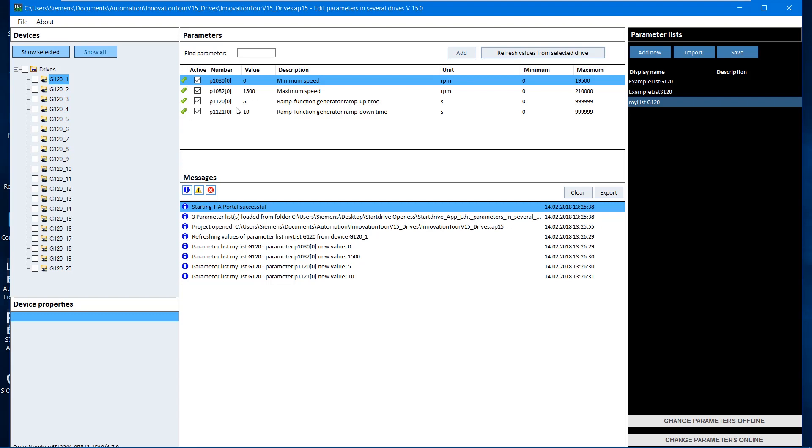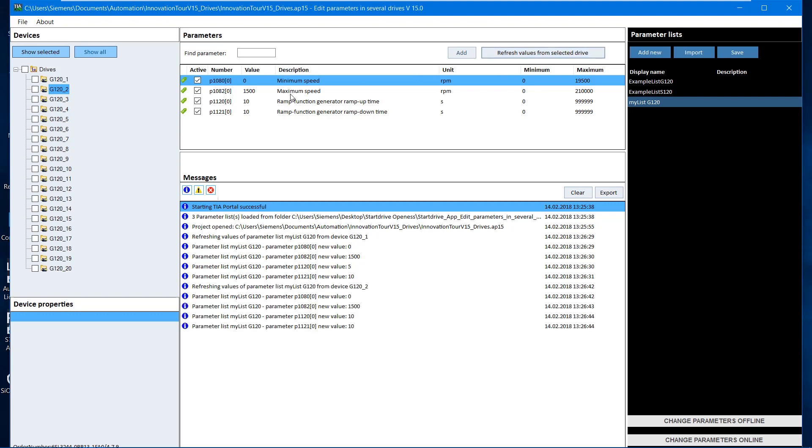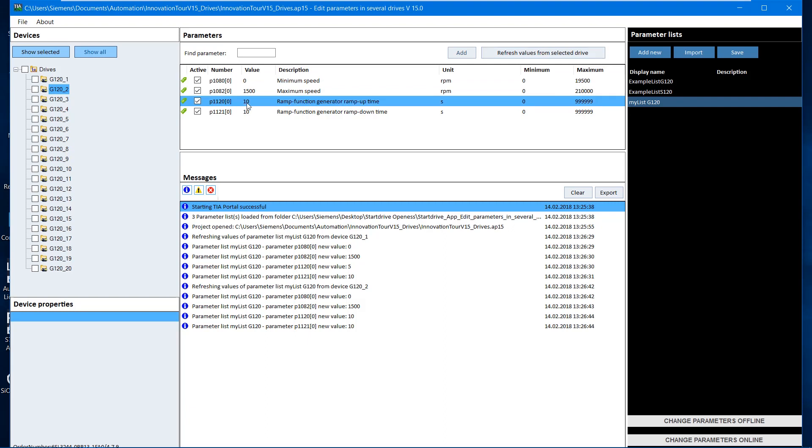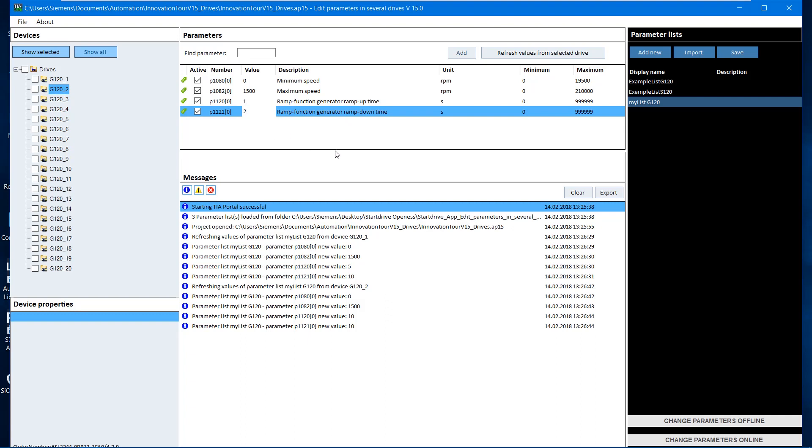It can now be seen that the ramp down and ramp up times are different, 5 and 10 seconds. Now we read the data from the second drive. Here the ramp up and ramp down times are 10 seconds. However, the set times are too high and in order to increase the product output of the machine, we want to set the ramp up time in all drives to 1 second and the ramp down time to 2 seconds.